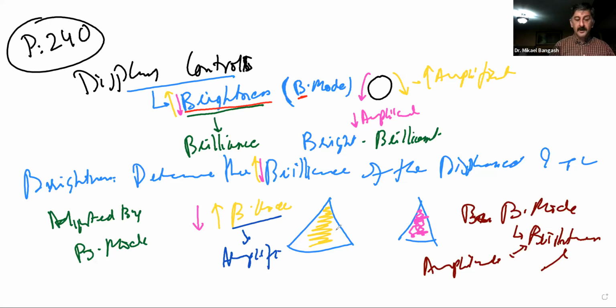Which will make your overall image brighter. Or on the other hand, you can reduce the brightness, you can reduce the brilliance by reducing the amplification, by reducing your B mode, which reduces the amplitude of the signals that were reflected. They were going to be amplified to a lesser extent. But this is mainly the knob by which we control one of the things on the display and say, this is how bright and this is how dark we want our image to be.